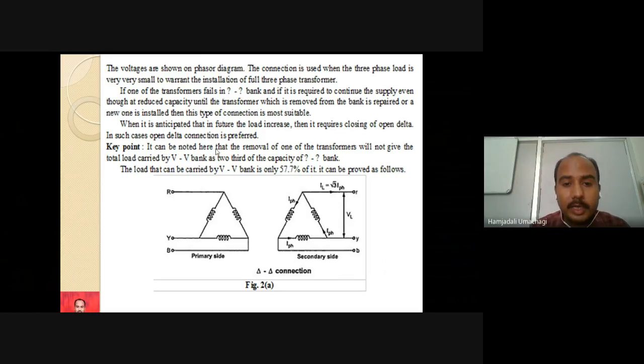Next, it can be noted that removal of one of the transformers will not give the total load carried by the VV bank as 2/3 of the capacity of the delta bank. Usually we are under the mindset that if any one of the three single phase transformers goes out of service, two transformers are still ready, and earlier it was three, so we think it can share 2/3 of the capacity. But this is not the fact. It is not going to support a load kVA rating of 2/3. But how much it can carry safely, we can see here.